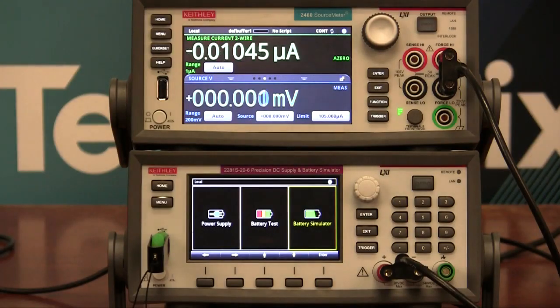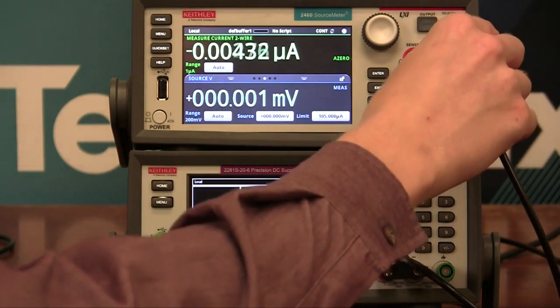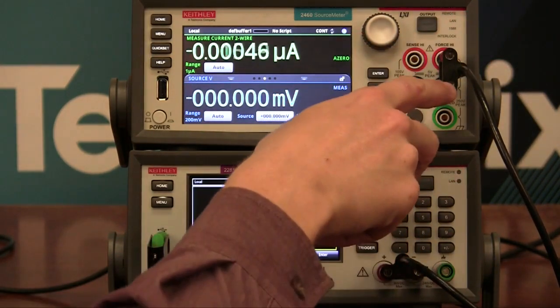So for this demo, you're going to need to connect up your 2281 to your 2450, 2460, or 2461, high terminal to high terminal, and low terminal to low terminal.